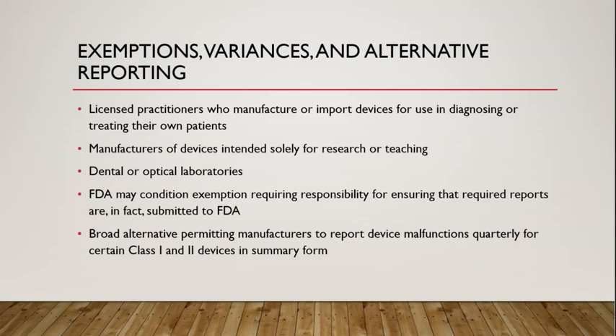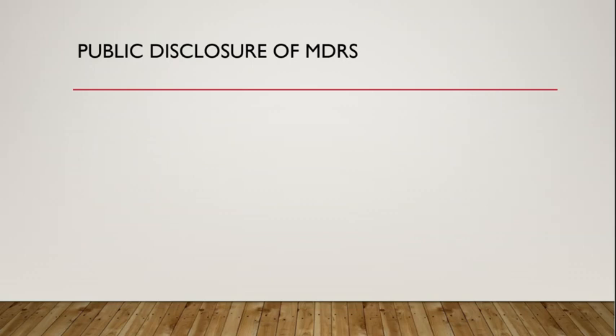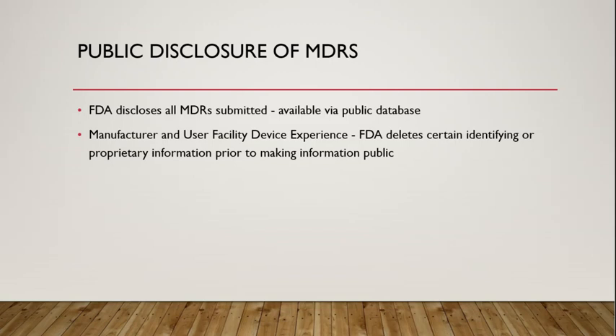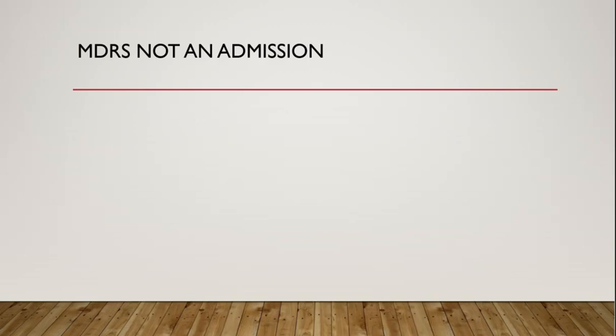One thing you always want to remember is that MDRs are subject to public disclosure, and FDA has disclosed and will disclose all MDRs that are submitted, and they're available by a public database. In fact, you'll see in your resource material in this week's Blackboard materials a link to the FDA database where you can get disclosure of MDRs. The other thing that's available is the manufacturer and user facility device experience. That's edited somewhat because FDA will delete certain identifying or proprietary information before that information is made public.